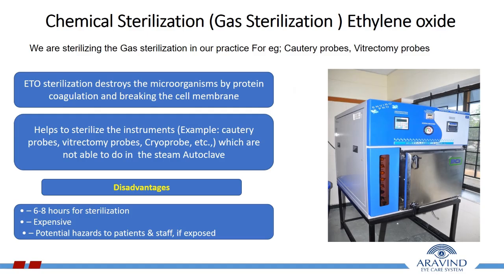Chemical sterilization, ethylene oxide. We are using gas sterilization in our practice, for example, for cautery probes, vitrectomy probes, etc., which cannot be done in the steam autoclave. ETO sterilization destroys microorganisms by protein coagulation and breaking the cell membrane. Disadvantages: 6 to 8 hours for sterilization in a long cycle, expensive, and potential hazards to patients and staff if exposed. Let me show you a video about ETO and sterilization.